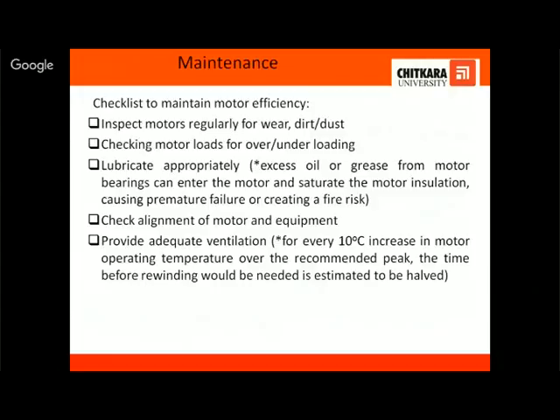Maintenance plays a very important role. When you have to audit, just check how the equipment and machinery is maintained. There is a checklist to maintain the motor efficiency. First, inspect motors regularly for wear, dirt and dust. Check the motors for overloading and underloading, so that a complete recording can be taken of the current flowing in the motor. From that we can work out the percentage loading of the motor, and we can plot our own curves to find out the load pattern of the motor.